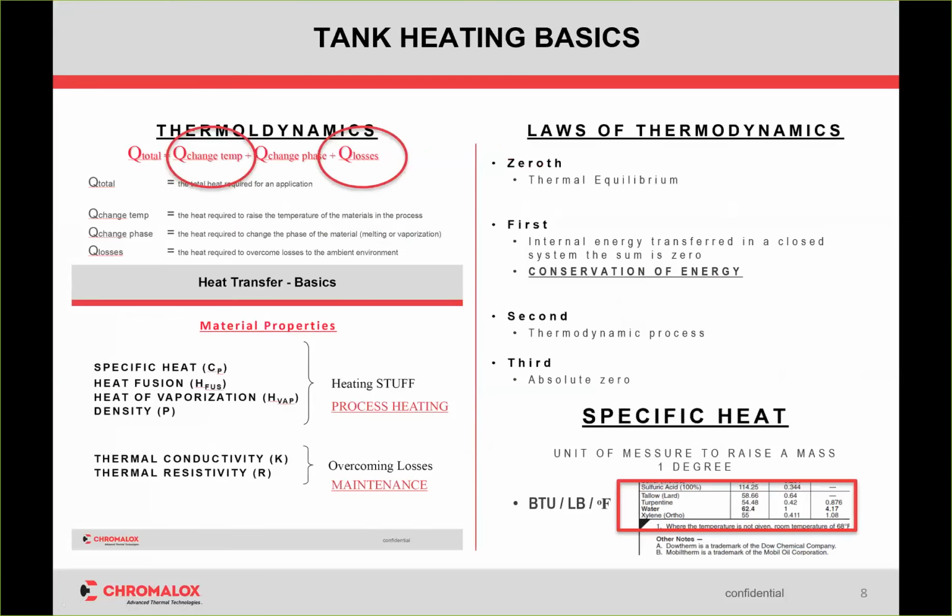So think of heat up and heat loss in the case of tank heating. They all follow the rules of thermodynamics. We're mostly focusing on the first rule, which is the summation of zero. You're losing heat to the environment, or you're trying to heat something up, so you're trying to get the equation to equal out. As we go through, it's important to remember that the measure of specific heat is based off of water, and that is one thermal BTU per pound per degree F temperature rise for water, and then everything else is kind of interpolated off of that for your different components.